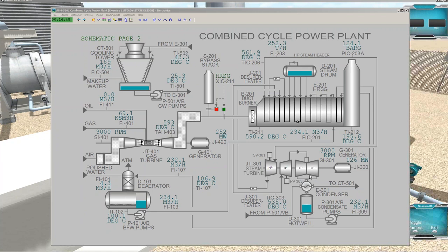The exhaust steam from the low pressure stage is then condensed in the surface condenser using circulating cooling water. That's the 4th section of the plant. And then the cooling water goes around to a cooling tower with cooling water circulation pumps. So we have that integration in with the condenser.